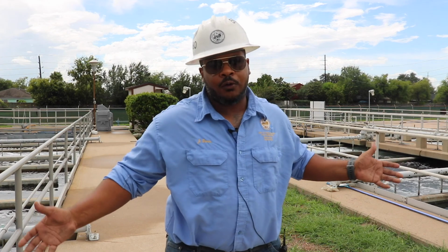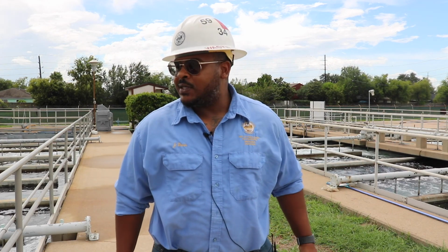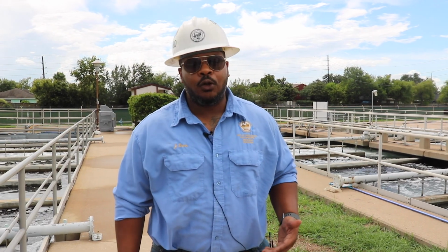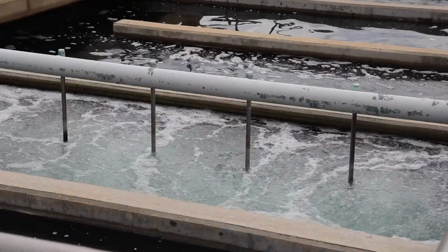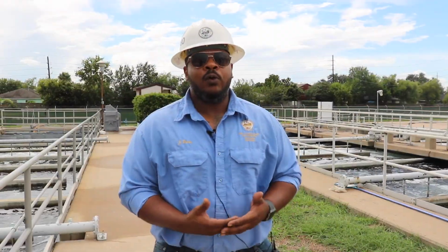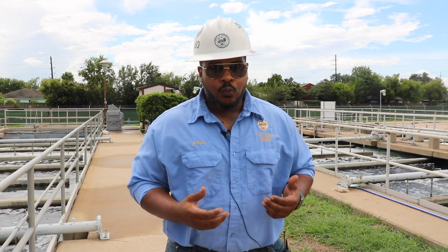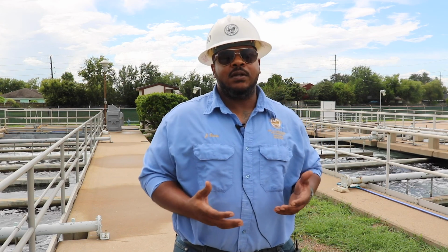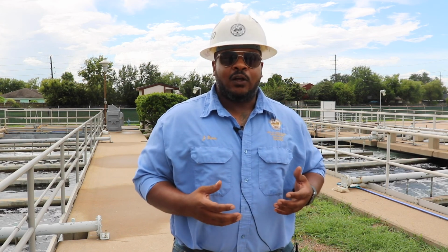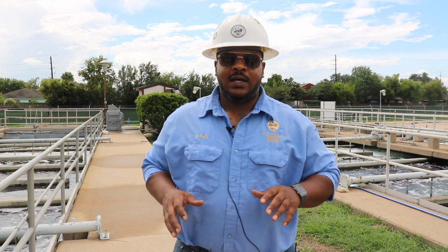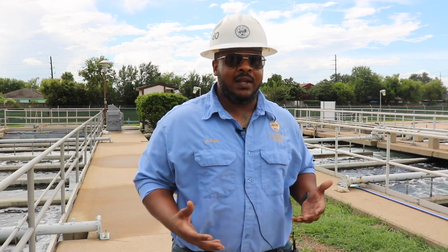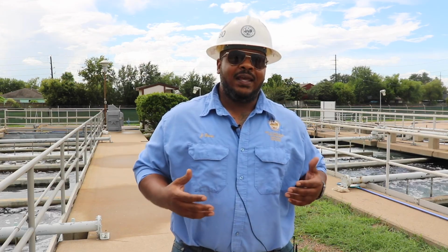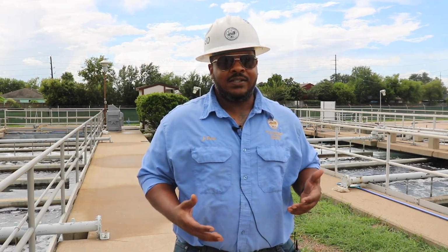These are our chlorine contact basins. What happens here is chlorine is introduced to kill any bacteria or any waterborne pathogens. What we really have, the most important thing is a 20-minute detention time. So that means once chlorine is introduced, before it leaves and is neutralized by sodium bisulfite, it sits in here and it mixes for 20 minutes. With that 20 minutes, it kills all waterborne pathogens.